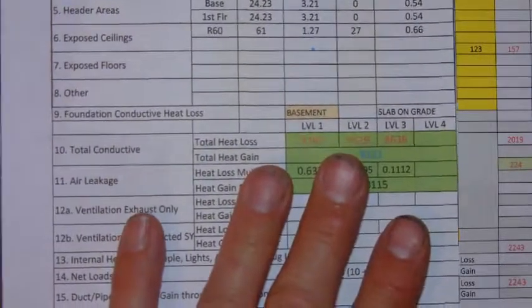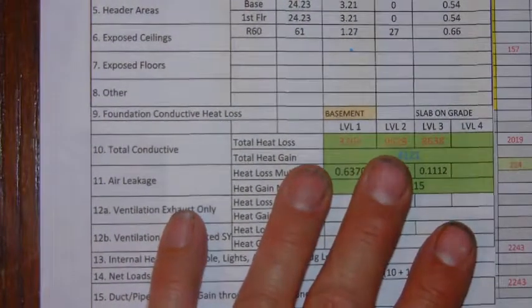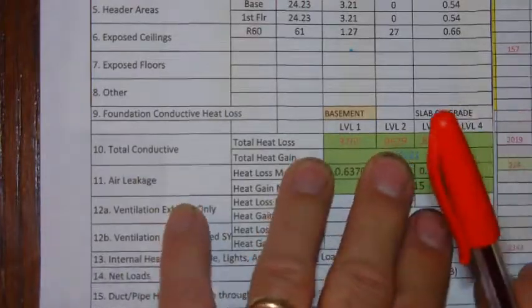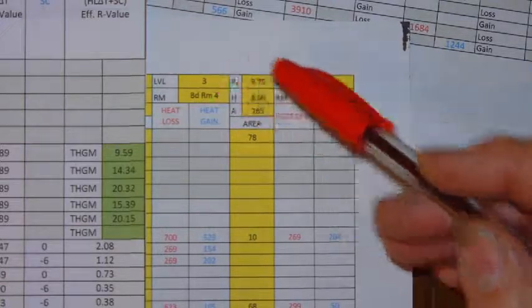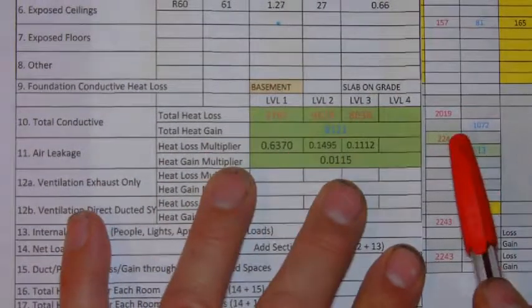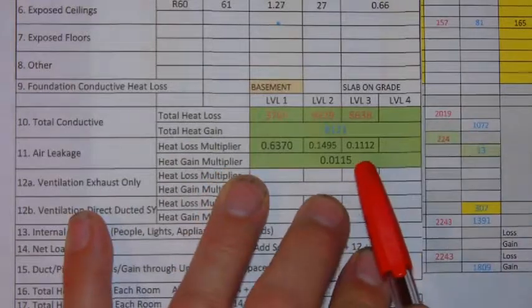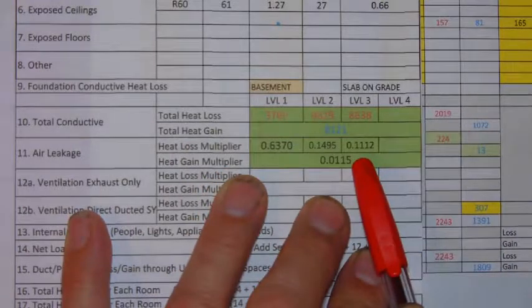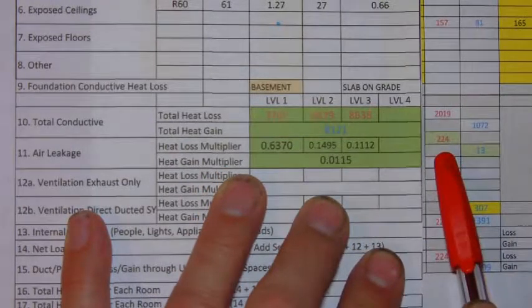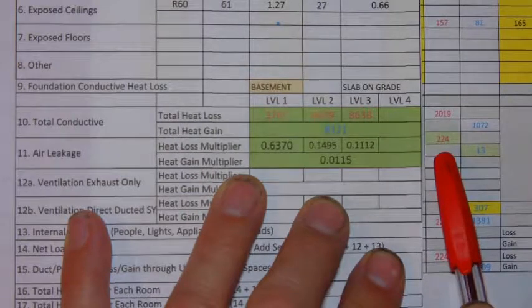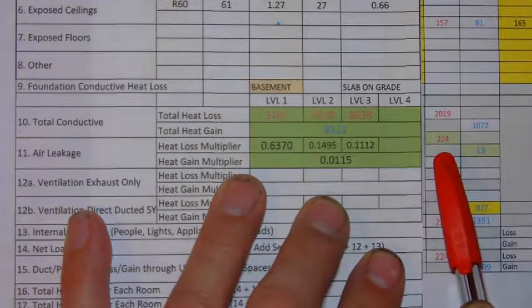And just if we looked at another room, say bedroom four. Bedroom four is on level three. So again, you'll use the level three multiplier. So 2019 times 0.1112 gives us 224 BTUs.